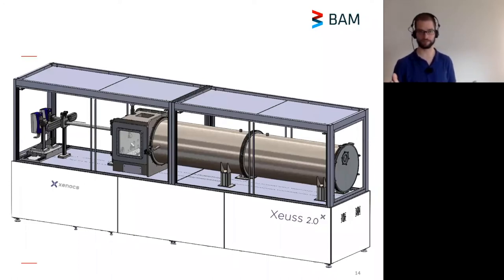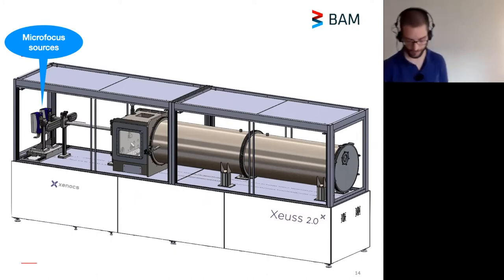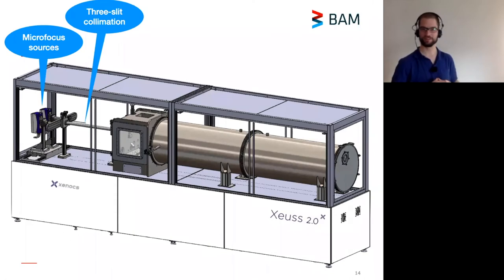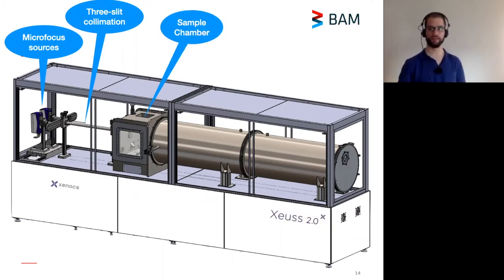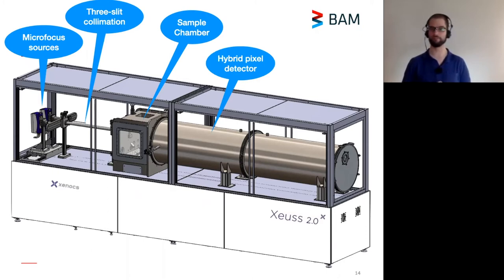The machines very much reflect this principle. Our machine has two x-ray sources — a copper source and a molybdenum source — so we have different x-ray photon energies we can play around with, which has turned out to be more useful than I thought. There is a three-slit collimation after the monochromator attached to the sources, with which we can cut down the beam to whatever size and shape we want. We have a very large vacuum sample chamber, and at the end there is a hybrid pixel detector on a motorized carriage so we can move it backwards, forwards, and sideways.